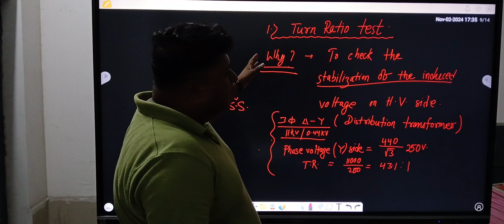So keeping the tap position in the required tap, suppose we are going to test in tap 1, then tap 3. Normally we are doing randomly, we are doing for 1, 3 and 17 to check the turn ratio. We can do for all the tappings as well, no problem. So if we are going to test for a certain tap, let it be tap 1, we are keeping the transformer in that tap position, that is step 1.